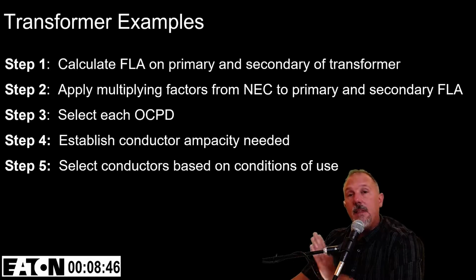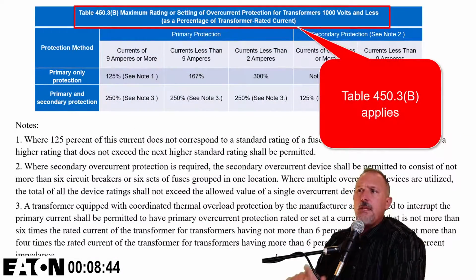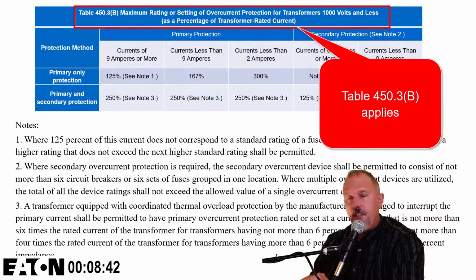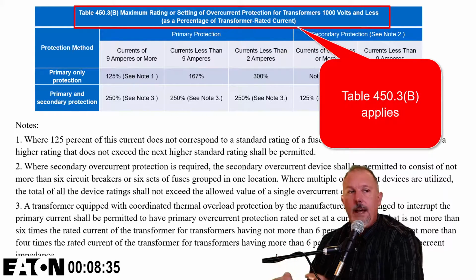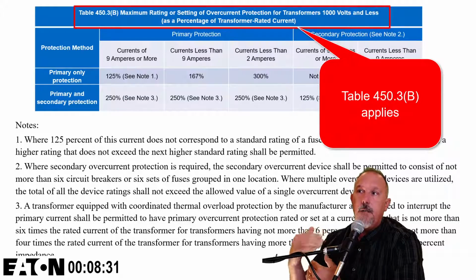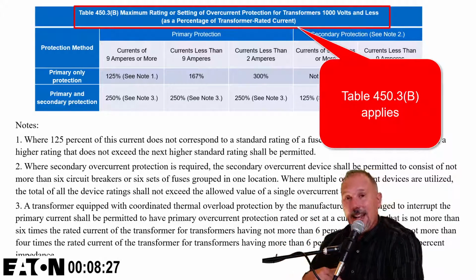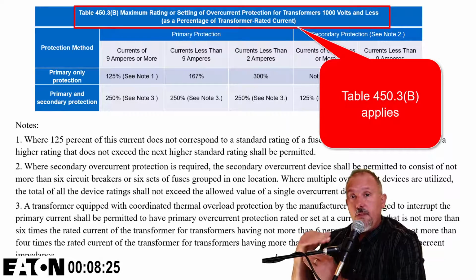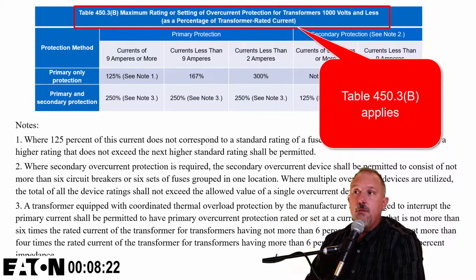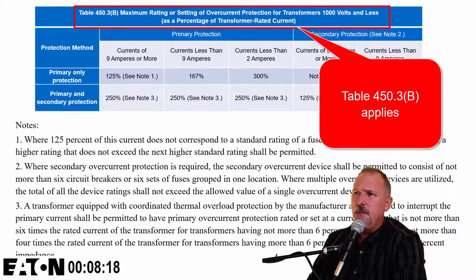Now I have to apply the multiplying factors. And I go to Article 450 because that deals with transformers. And I use 450.3(B). I don't go to 450.3(A). Why? Because A is medium voltage. B is 1,000 volts and less. Remember, we moved that 600 volts up to 1,000 volts, I think it was a couple cycles ago, maybe last cycle. No, 2 cycles ago.